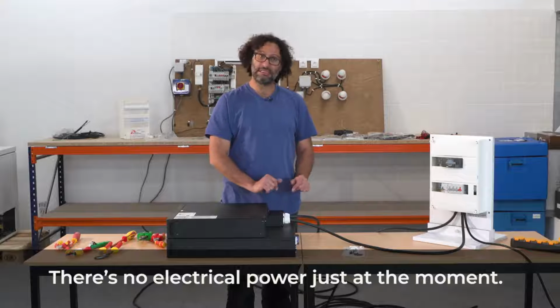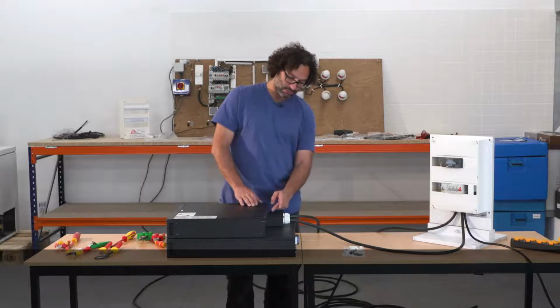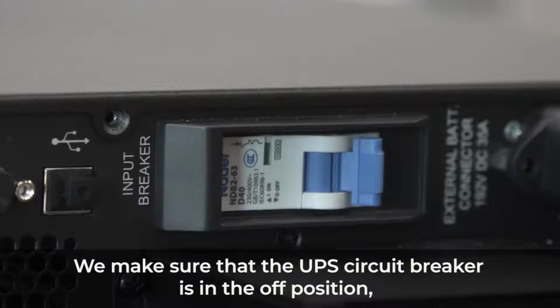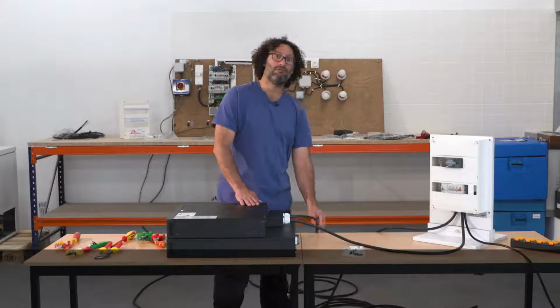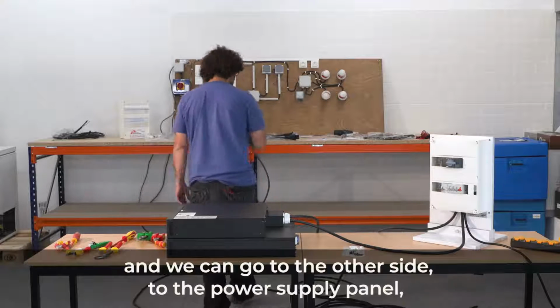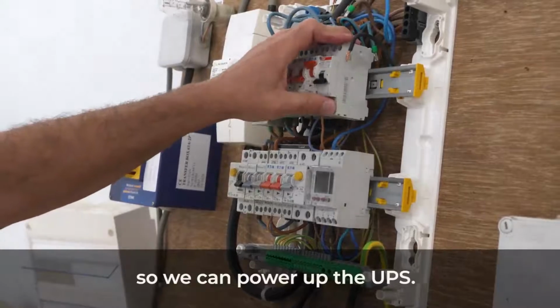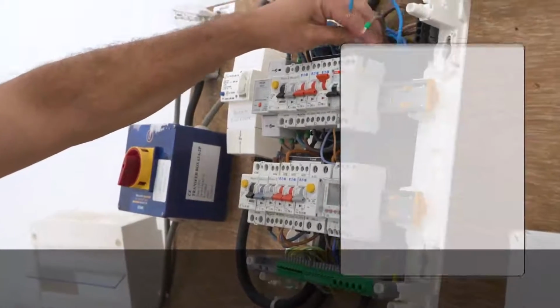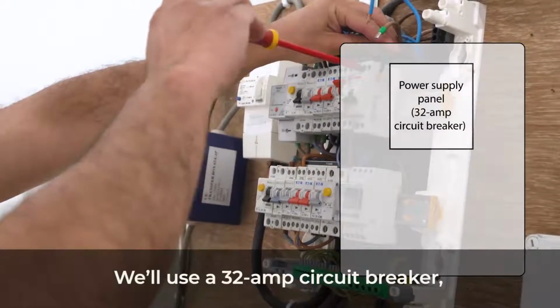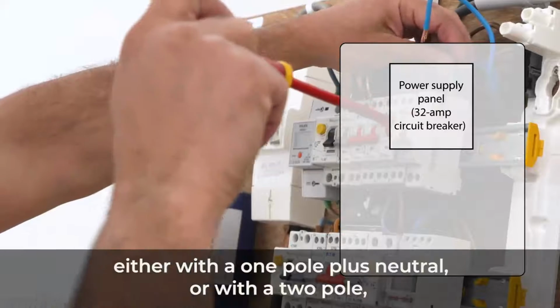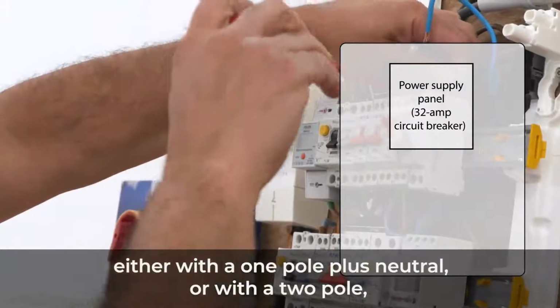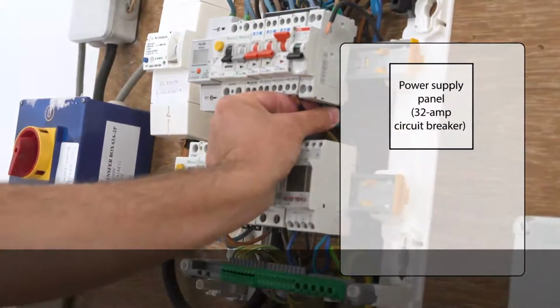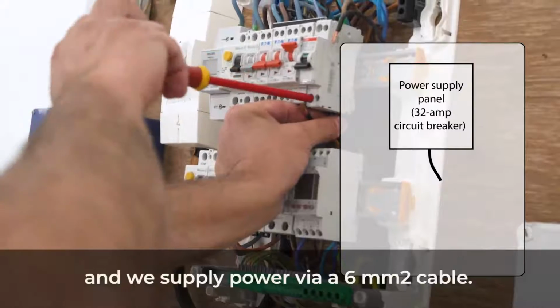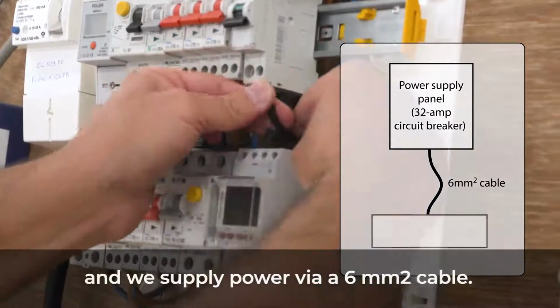There's no electrical power just at the moment. We make sure that the UPS circuit breaker is in the off position and we can go to the other side, to the power supply panel, so we can power up the UPS. We'll use a 32 amp circuit breaker, either with a 1-pole plus neutral or with a 2-pole. And we supply power via a 6mm squared cable.